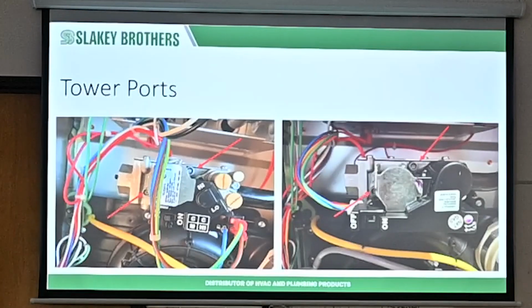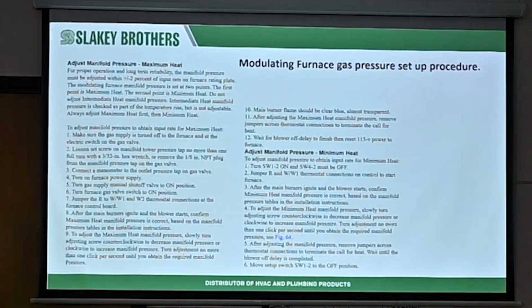It will never overheat, because both of these units, the Evolution line units, have an ECM constant airflow motor, so they will constantly get you the right airflow at all times. Okay. All right. So this here, it's in the install manual. It's going to be really, really small to read here, but it's just step by step of how to adjust the gas pressure on the modulating furnace.